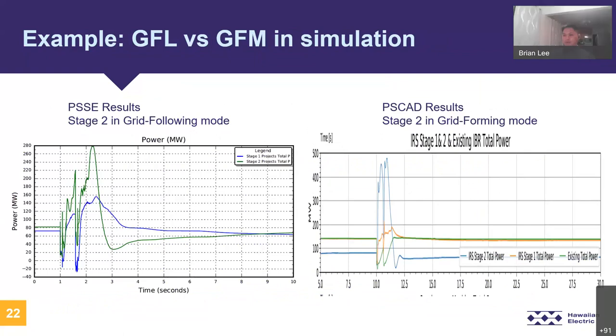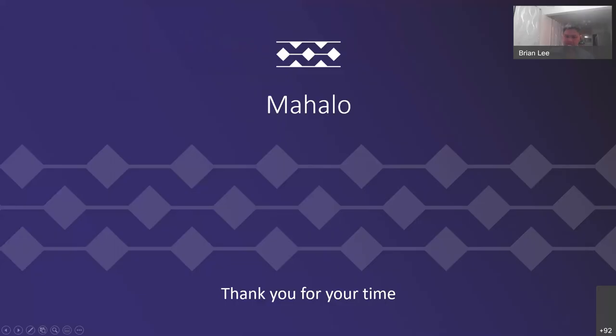Here's just an example of a grid following and grid forming comparison that we've been seeing in our current study. We can see grid following is on the left, grid forming is on the right. This is the same contingency, but the grid forming response is almost immediate versus grid following. This is a really good demonstration of what we want for our system, because we are islanded systems. As we move towards renewables and 100% IBR, we're going to displace a lot of traditional synchronous machines with inertia. So we want this fast response from the grid forming IBRs. That's all I had. Thank you.